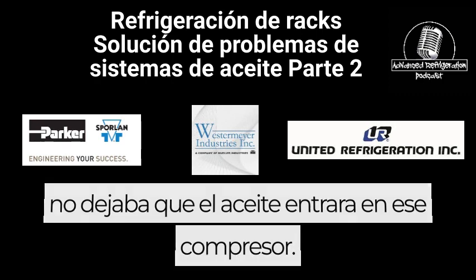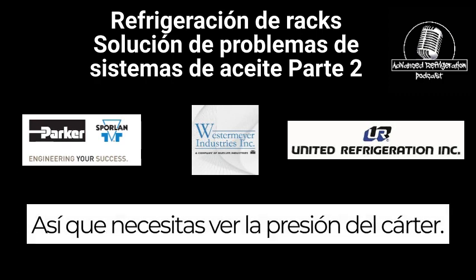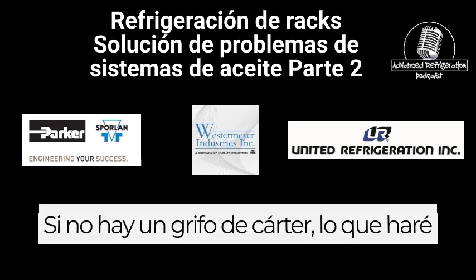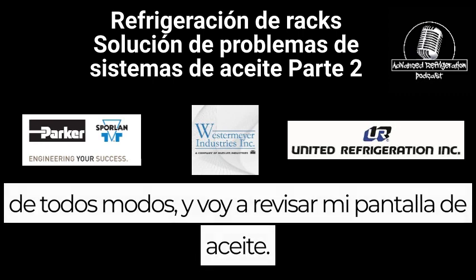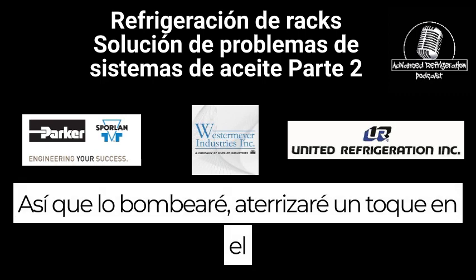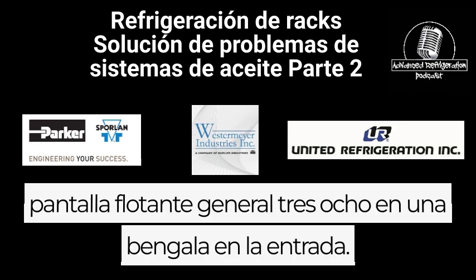and it would not let oil feed into that compressor. So you need to actually see the crankcase pressure. If there's not a crankcase tap, what I will generally do, I'm going to pump the compressor down anyway, and I'm going to check my oil screen. So I'll pump it down, I'll land a tap at the same time as the crankcase, and then I will pull the screen on the float. Generally, it's a 3/8 screen on a flare.